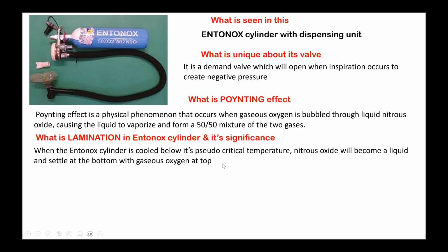Nitrous oxide will become liquid and settle at the bottom, and oxygen will remain at the top, so it becomes two layers, or lamina. The gas will be the top layer, which is purely oxygen, and the liquid will be at the bottom. Normally in the Entonox cylinder, both should be in the gaseous form at a concentration of 50-50. Whereas once lamination occurs, the cylinder becomes cool, the nitrous oxide will become liquid again and settle down at the bottom. So if you don't take precaution and use that cylinder, the patient will receive only pure oxygen in the beginning, and later the nitrous oxide will start becoming a gas, and you will get a hypoxic mixture with more nitrous oxide. That is called lamination.